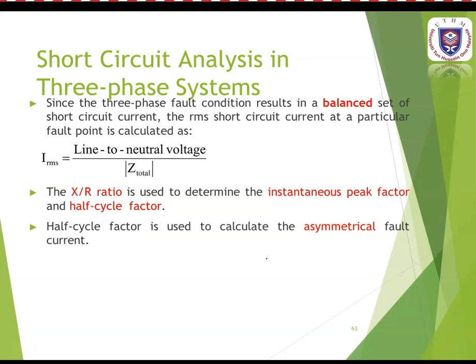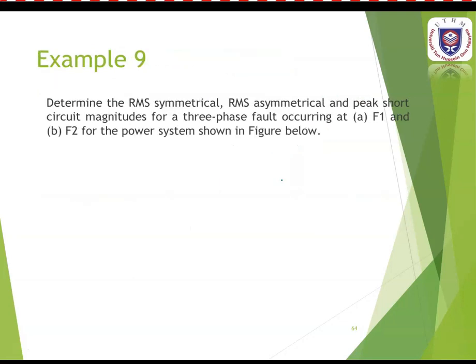Since a three-phase fault results in a balanced set of short circuit currents, the RMS short circuit current at a fault point is calculated as IRMS = V-phase divided by the magnitude of the total impedance. The X/R ratio is used to determine the instantaneous peak factor and half-cycle factor. The half-cycle factor is used to calculate the asymmetrical fault current. Example 9 requires determining RMS symmetrical, RMS asymmetrical, and peak short circuit magnitudes for faults at F1 and F2.